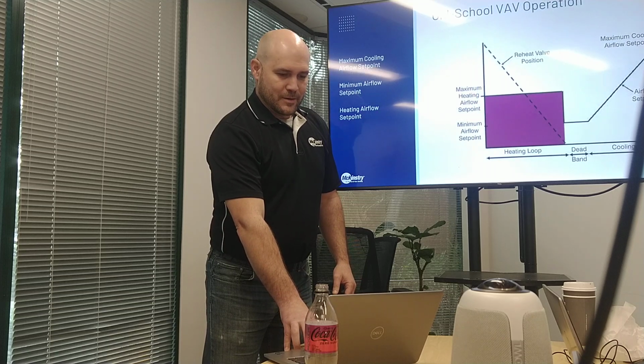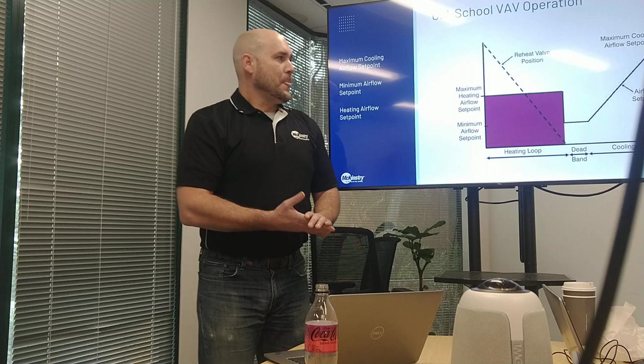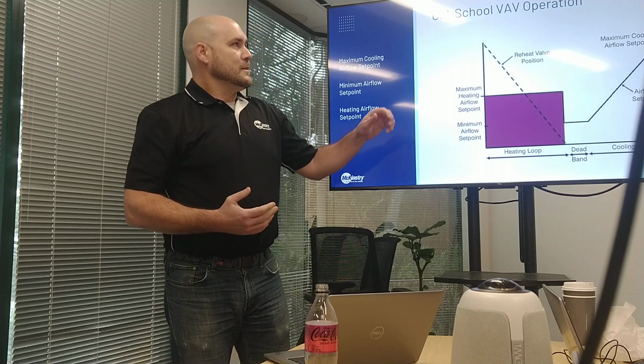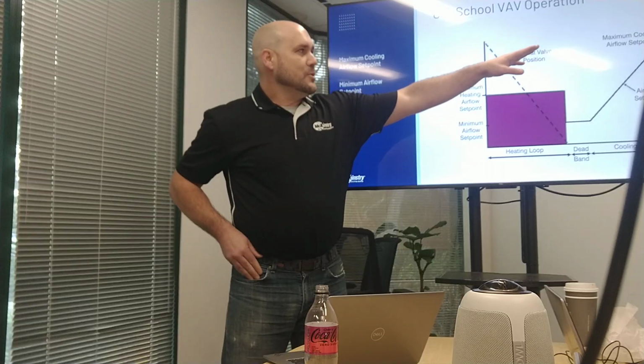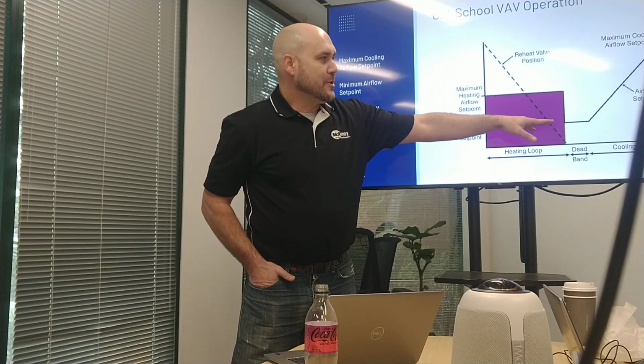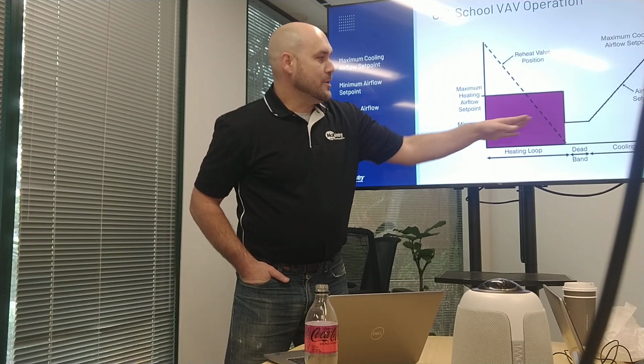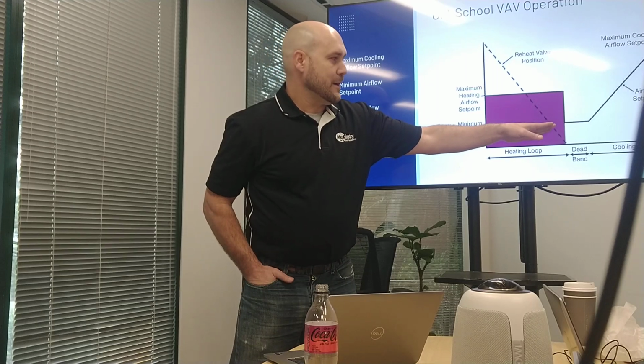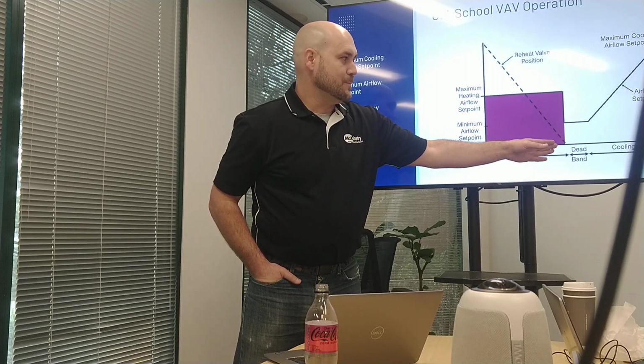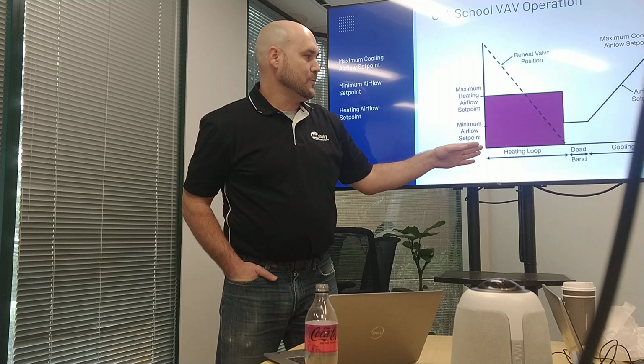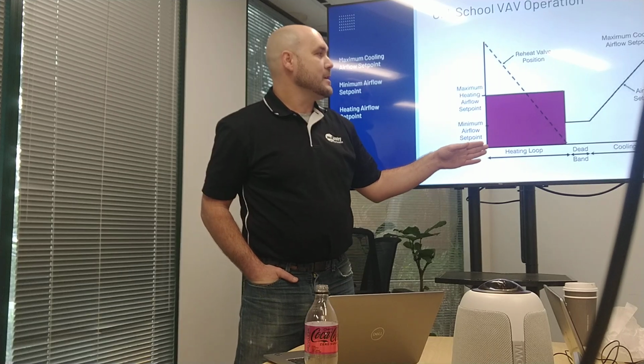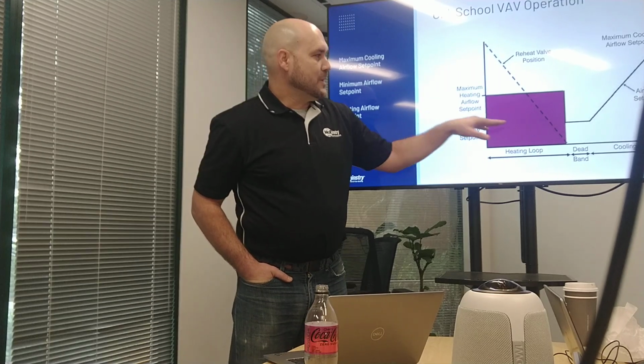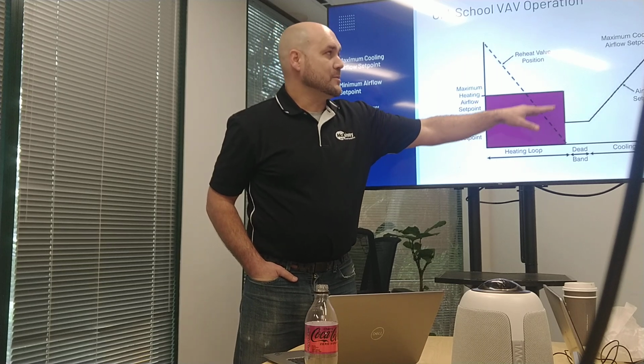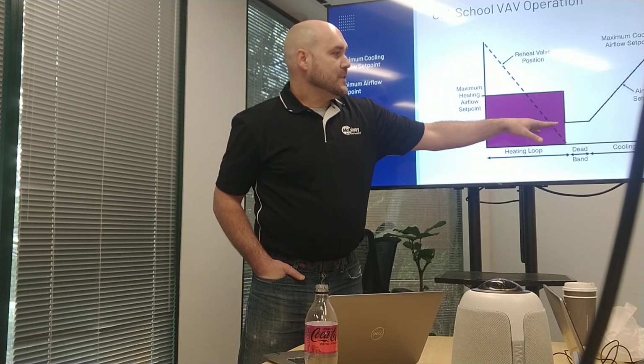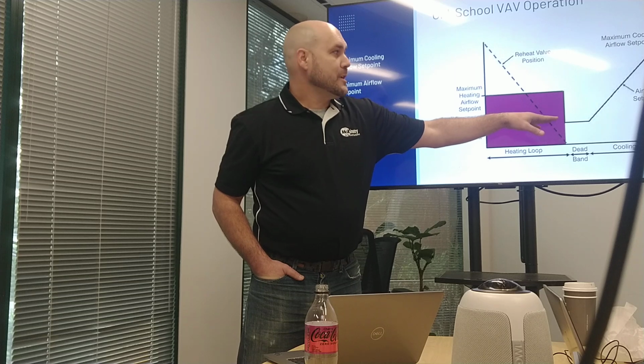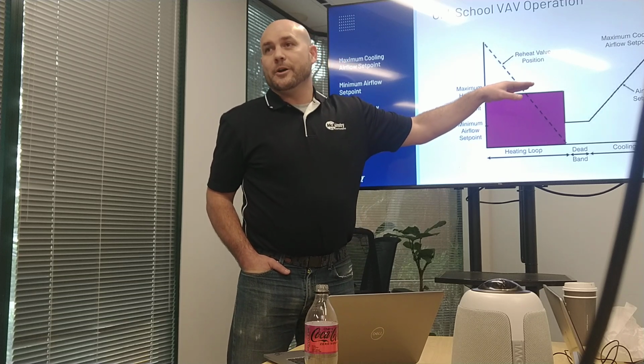Stepping forward a little bit in time, you see that you still have the maximum cooling airflow set point, you still have a minimum airflow, but then when you get into heating mode, whether you have just a modest call for heat or a full scream for heat, the airflow set point steps up to something above the minimum. So that might still be 1,000. This might still be like 300, and then the heating airflow set point might be 400.